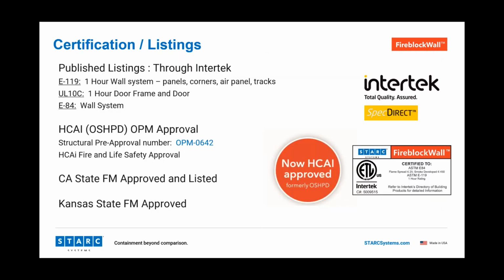For fire block, we've worked closely with Intertek for testing and our listings towards the principal E119 and E84 Class A certifications. And we have a separate certification for the UL10C 1 hour rated door frame. And then we use a commercial 1 hour door to go with that. We've also been working closely with regulators in Kansas and California to gain their approvals. California's healthcare regulatory body, known as HCAI, or used to be OSHPD, has approved our system for both a seismic and fire life safety standpoint.